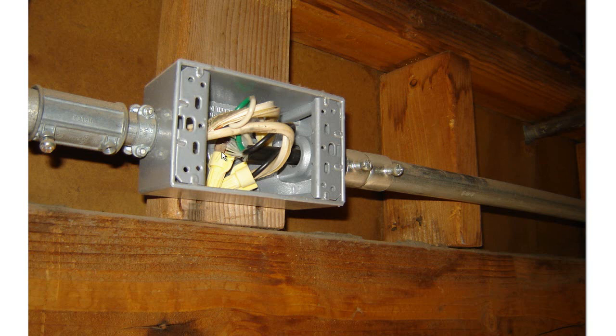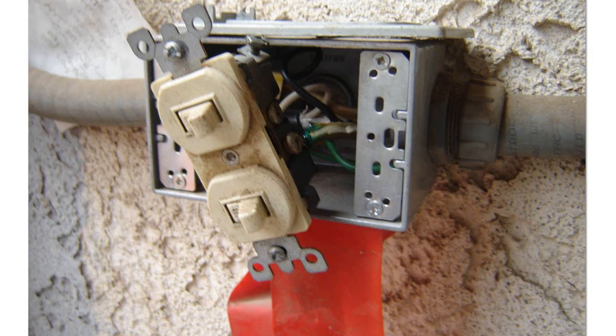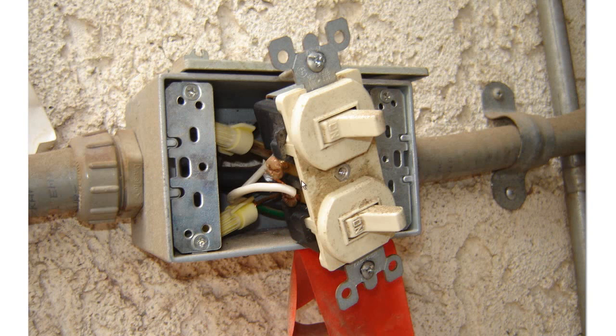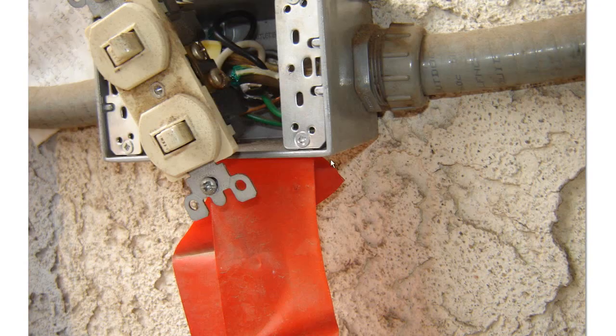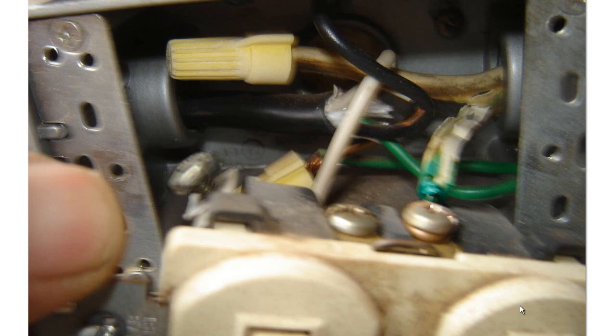Another close-up shot of it going in there, back into that wonderful conduit. Here's the switch. The switch wasn't even grounded. There's corrosion buildup all over this. They did a line and a load off this one particular toggle right here. Here's your view from the other side. They've got a line and a load, but they're not even doing anything with that one. I think the next picture shows us this black is just tied into a wire nut going up and feeding all the way out to the motor. That one's a little blurry, but you can see that this is just tied through, and they actually switched one of these going out.